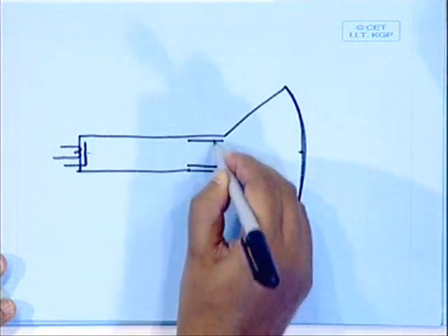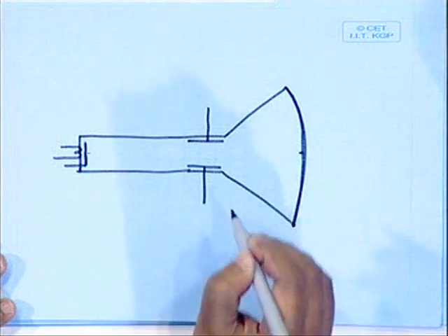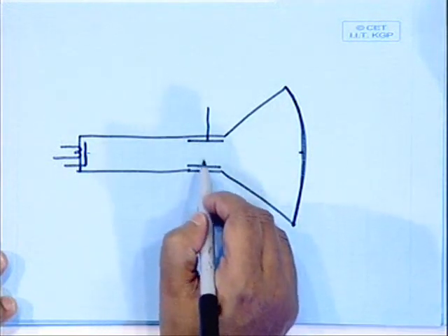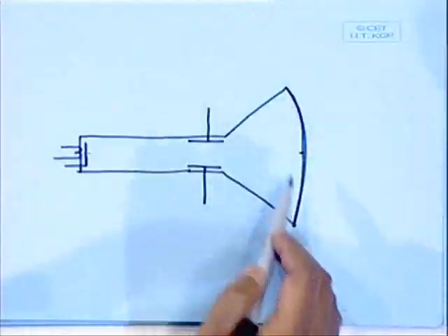We have one set of deflection plates or coils, and exactly 90 degrees to it another set. One set directs the beam horizontally, the other pair directs the beam vertically. Using the combination of the horizontal plates and the vertical plates, it is possible to move the beam to anywhere on the screen.